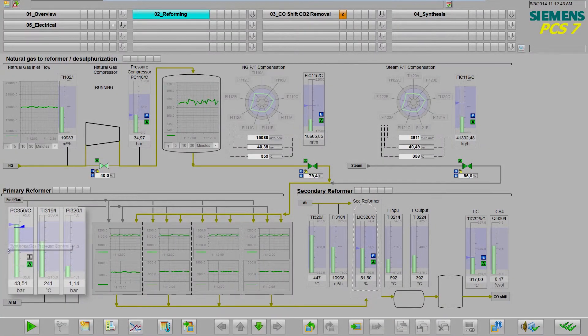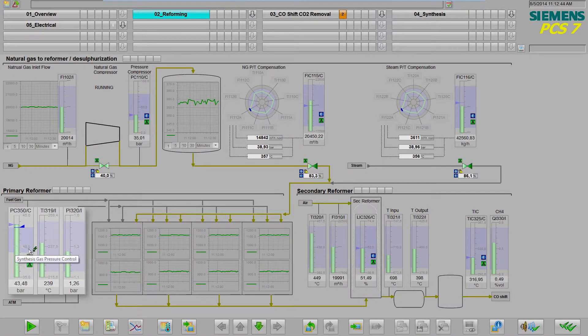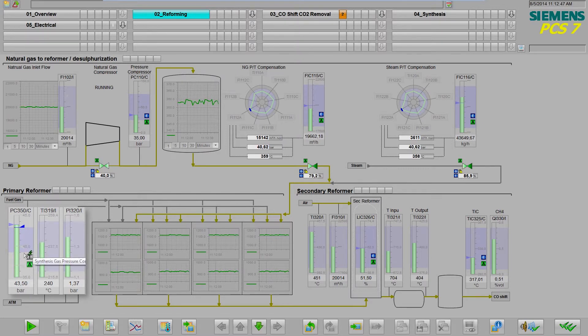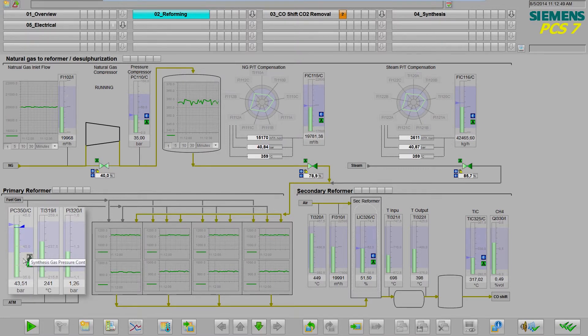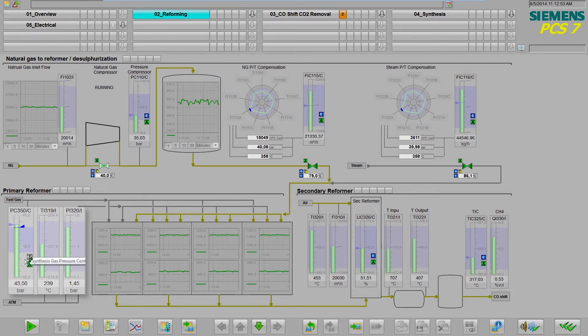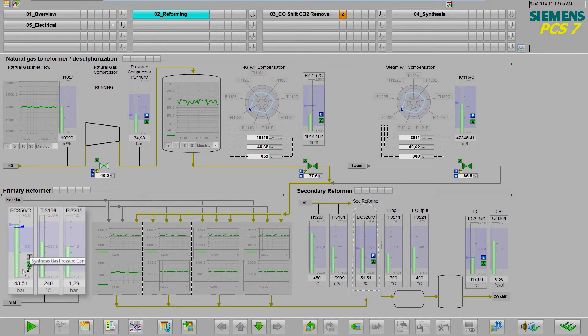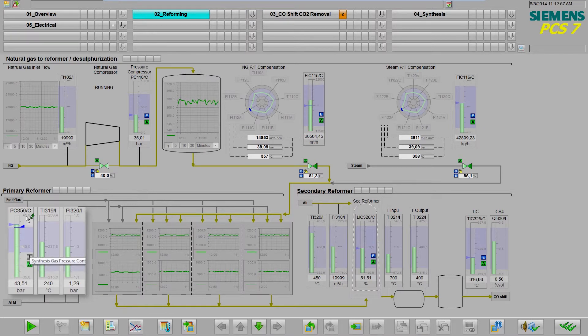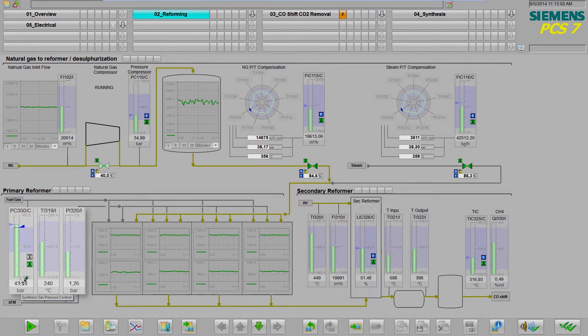The gas pressure display shows the optimal operating range, shown here in blue. Status information, such as manual or automatic mode, in the area on the right. A bar graph that is scaled to the display range rather than to the measuring range, in other words a zoom function. And the measured value and unit in the lower area of the bar graph.